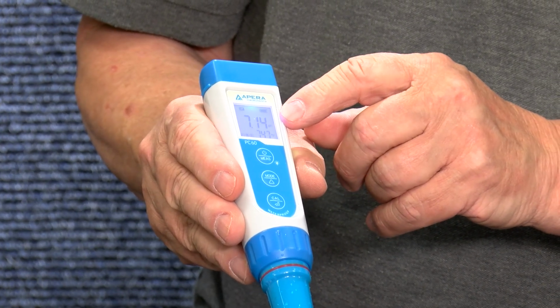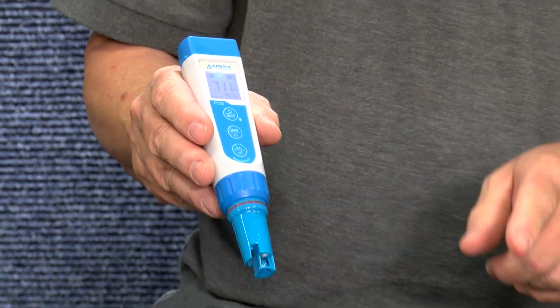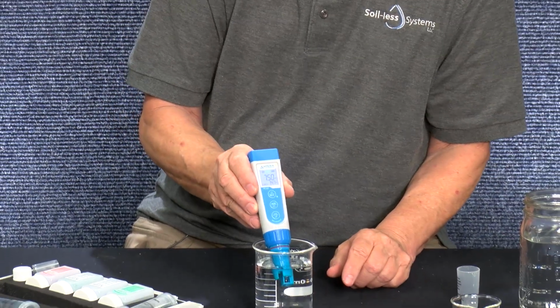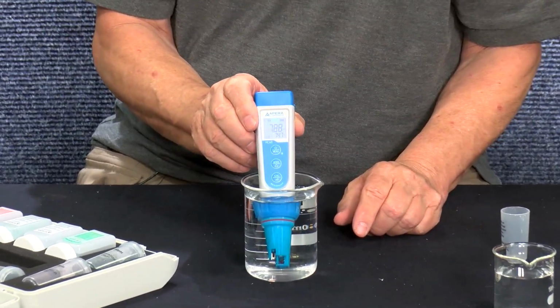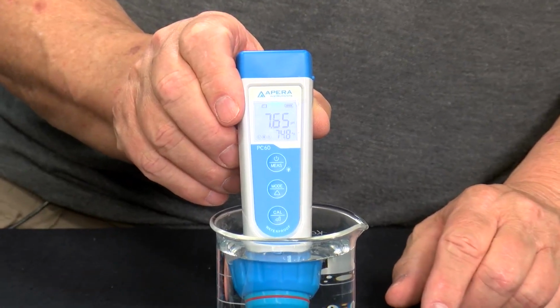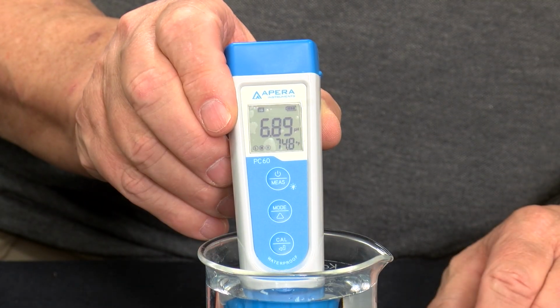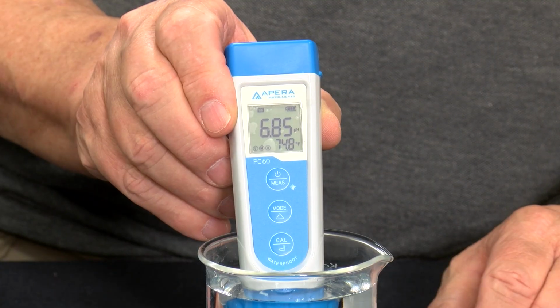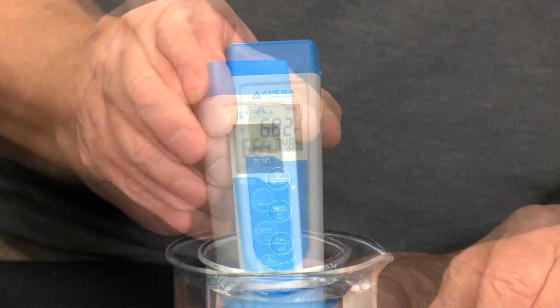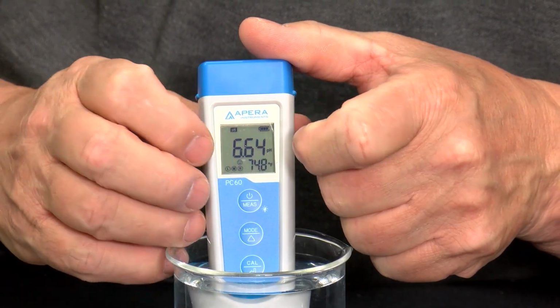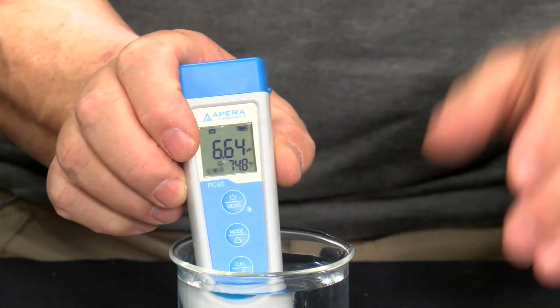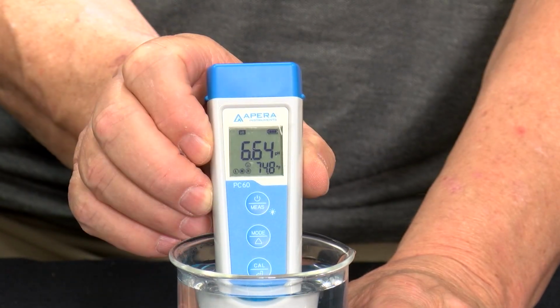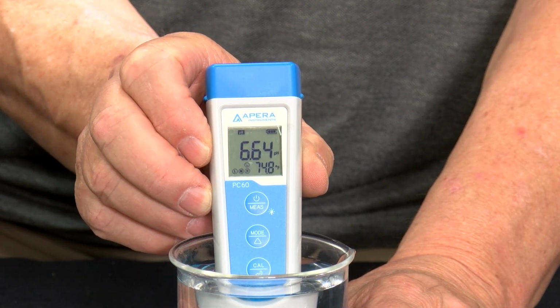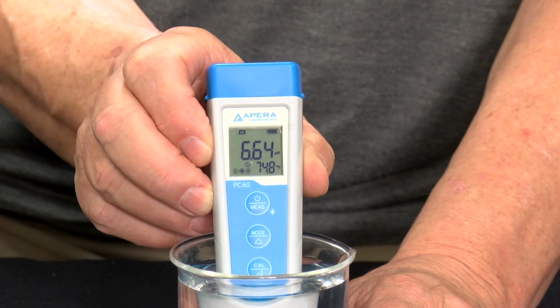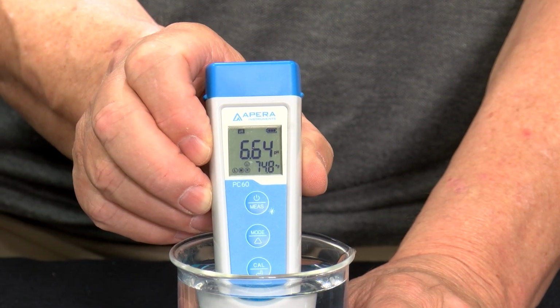Okay, so now we'll do a sample calibration. We have our sample water here, and we just put it into the liquid itself. There should be a little smiley face that comes on when it's steady. The little smiley face is right there, and it pops on when it's steady. In this case, our test sample is 6.64, which is in the range of RO water.